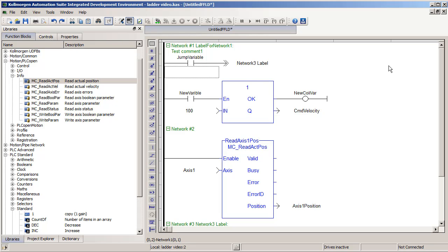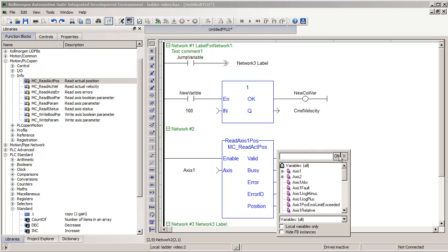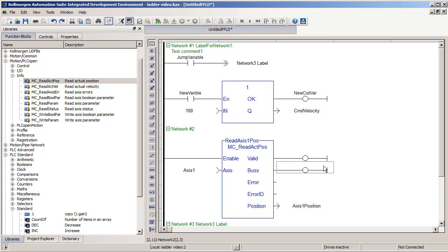Now we're going to go over some more advanced features that show why we call this a freeform ladder diagram editor, not just a standard ladder diagram editor. So what does that mean? Well, you may see right off the bat, we don't force you into a very rigid structure where you have to go contact, function block, coil. We don't force you to add anything to the outputs if you don't want to. Also, you can even put blank or empty coils, and in this way you can see the program animate with the power flow, but it'll compile without a variable even in there.